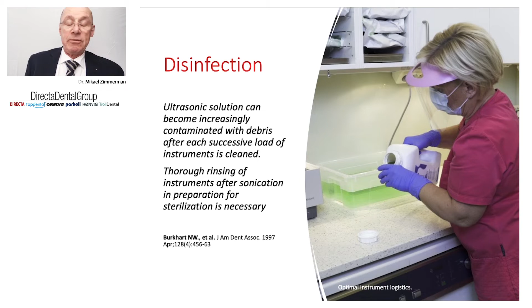The interesting thing with washer disinfectors is that they are generally computer-controlled units for cleaning, disinfecting, and drying solid and hollow surgical and medical instruments. And there are international norms and standards for how effective a washer disinfector must be in order to claim that it is a washer disinfector, also called a thermo disinfector. And there are also methods on how to validate the process to make sure that the washer disinfector is working in the right way.